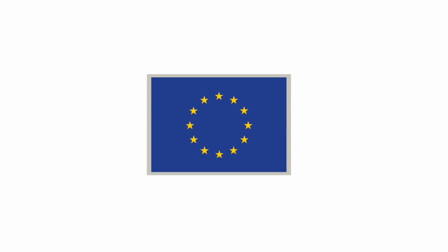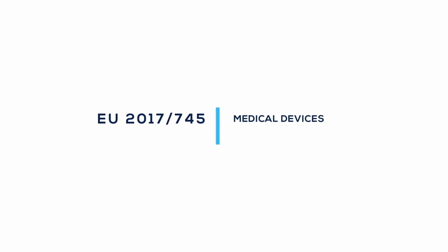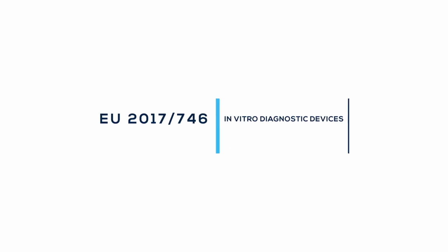Medical devices which are approved in the EU bear the CE mark to indicate that they comply with European regulations. The EU is currently transitioning to a new regulatory framework which will apply to all devices from May 2020. These regulations, referred to as EU 2017/745 for medical devices and 2017/746 for in vitro diagnostic devices, cover the design, manufacture, distribution and surveillance of all devices in the EU.